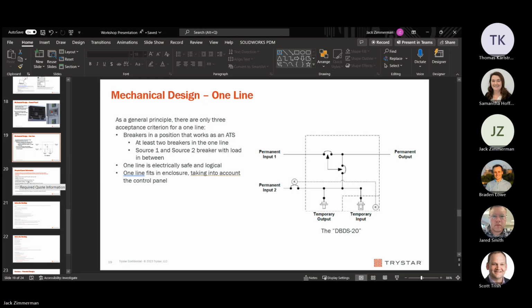So here's our one-line acceptance criteria. This is especially relevant for the electricians, and for the folks who do submittals. There are basically three acceptance criteria for the one-lines. First, the breaker's in a position that works as an ATS. We discussed that at length before, that little diagram with source 1, source 2, has to be in there somehow, with a load in between.